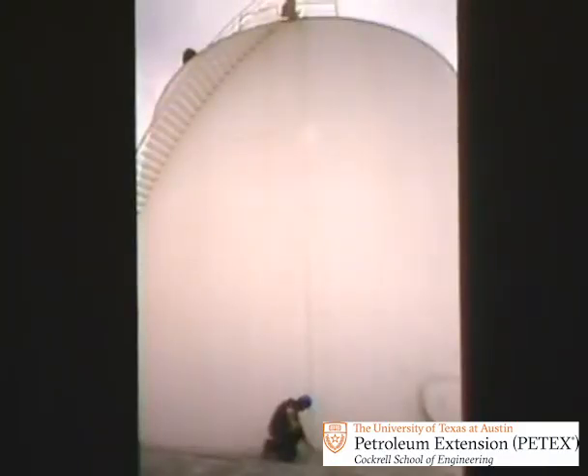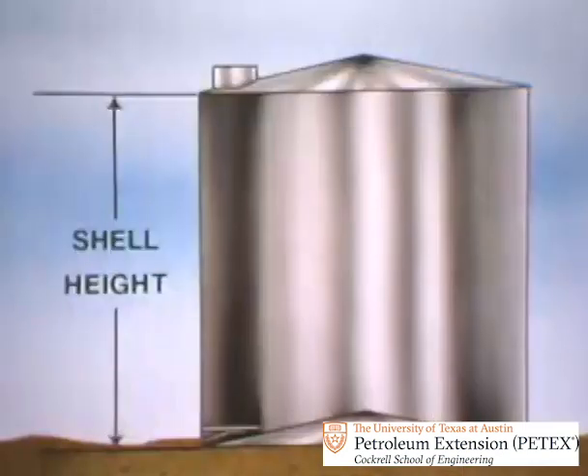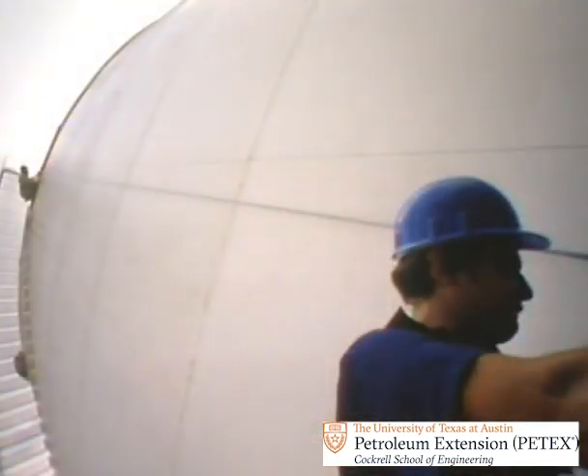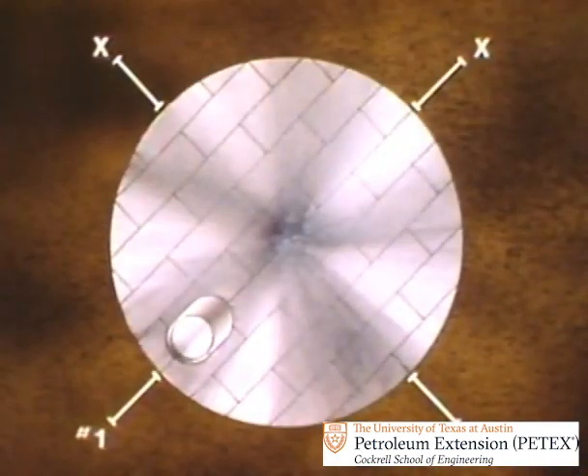The next procedure in the strapping operation is measuring the shell's height. Shell height is the distance between the bottom of the bottom angle and the top of the top angle. The crew measures shell height and plumbness near the hatch and at 3 other points of equal distance around the shell.